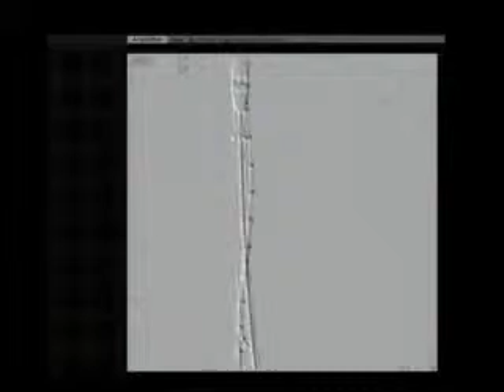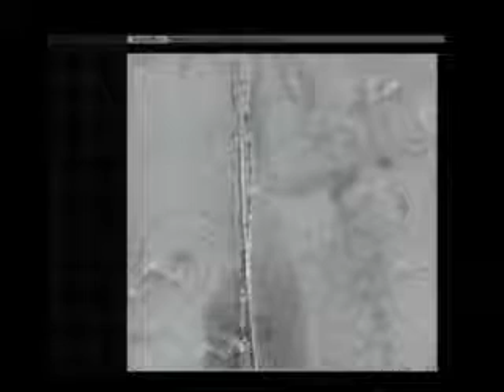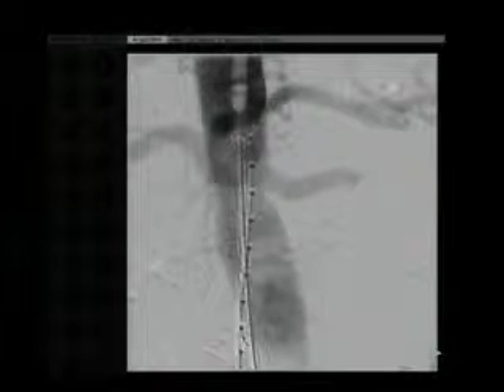Now we are going to do a DSA, getting the patient off the ventilator for a while we are doing the DSA. Now we see on the DSA that we are clearly above the renals. We pull back the device a little and then open the sheath, withdrawing the sheath by anti-clockwise movement of the blue handle.